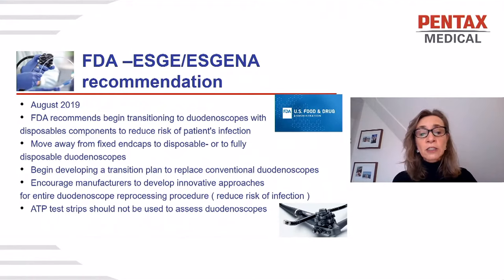Look at all the disposable accessories and begin developing a transition plan to replace the conventional duodenoscope with a fixed cap with one that has a disposable end cap, and encourage the manufacturers in this. Also, ATP tests should not be used to assess duodenoscopes - that's another step.